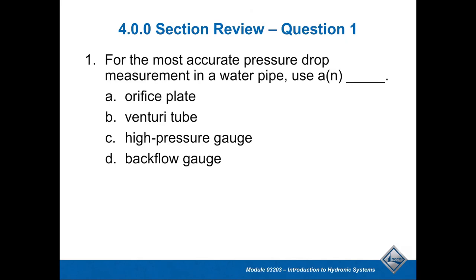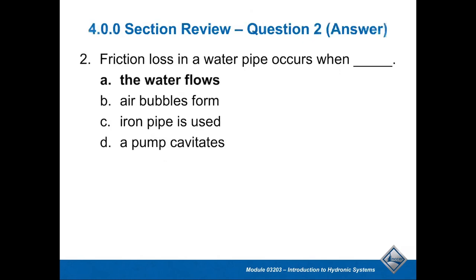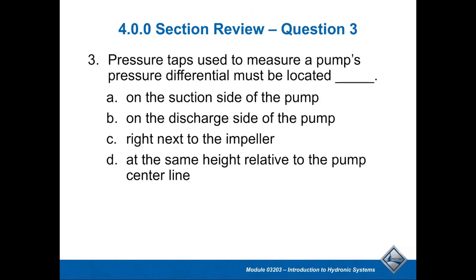For the most accurate pressure drop measurement of a water pipe, the Venturi tube makes the most sense. Friction loss in a water pipe system occurs when water flows. The pressure taps used to measure a pump's pressure differential must be located at the same height relative to the pump's centerline.